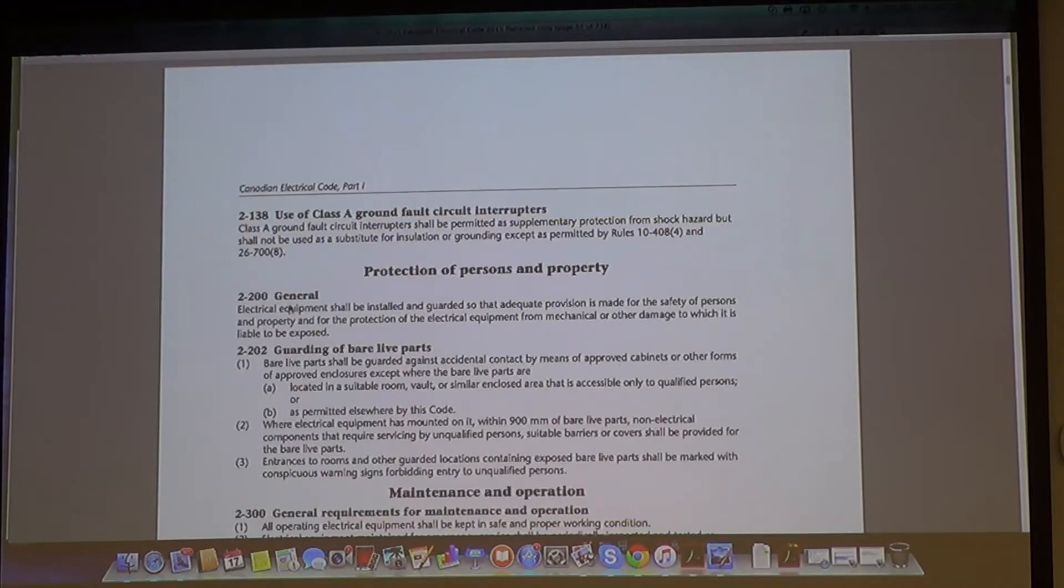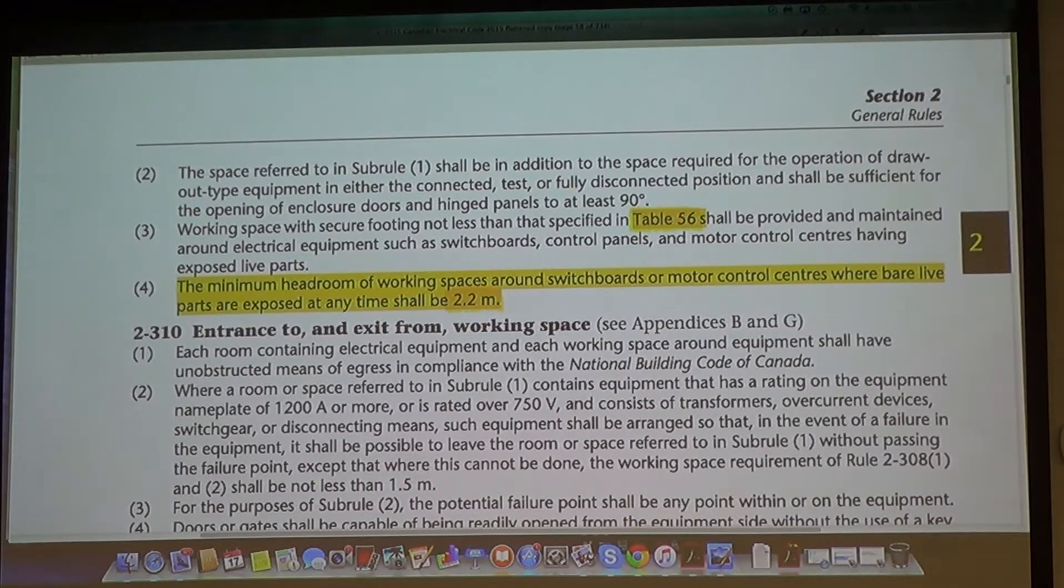What rule is that? 308 sub rule 4. Right here guys on the screen, okay? Minimum headroom clearance for workspace around switches, switchboards, or motor control centers where bare live parts are exposed is 2.2 meters.